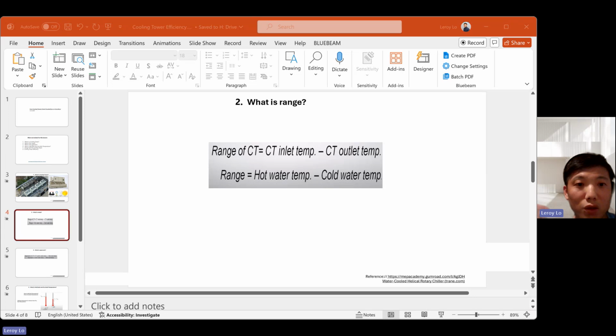So what is the range? The difference between the cooling tower inlet temperature, the hot water temperature, and the cooling tower outlet temperature, which is the cold water temperature, is called the range of the cooling tower. So the range of the cooling tower equals the cooling tower inlet temperature minus the cooling tower outlet temperature. Or you can say that the range equals the hot water temperature minus the cold water temperature. That's easier for me to understand. For example, normally you have hot water coming in at 95 degrees Fahrenheit, and you have cold water going out of the cooling tower at maybe 85 degrees Fahrenheit. That's easy to understand for most people. Moving on to the next.